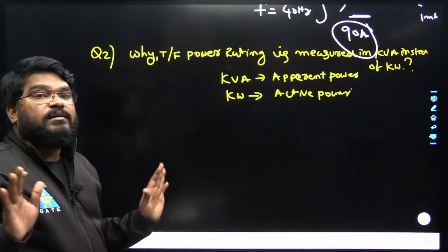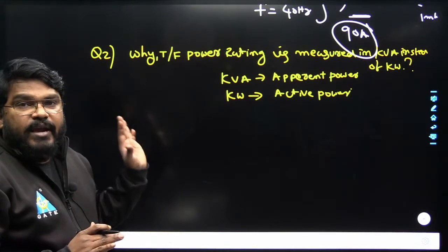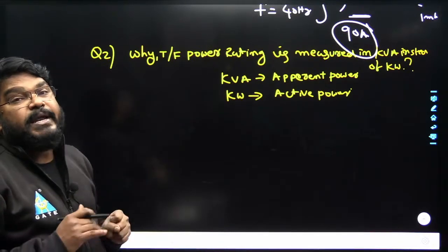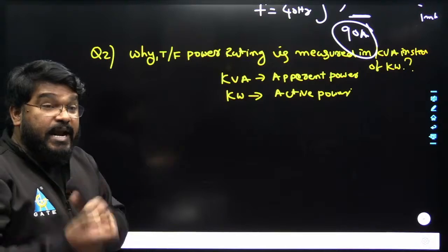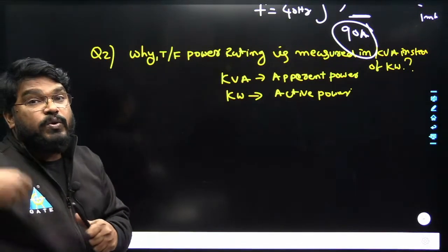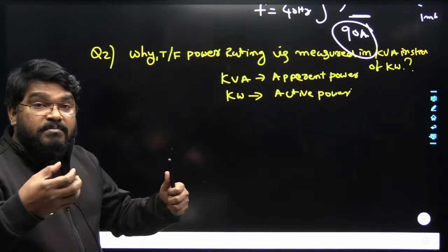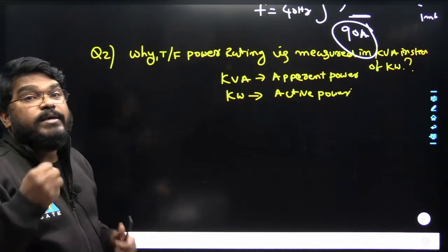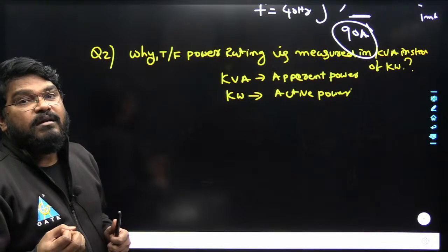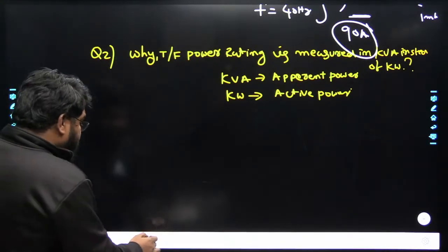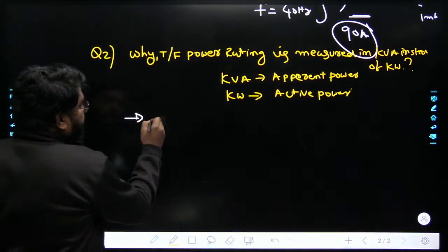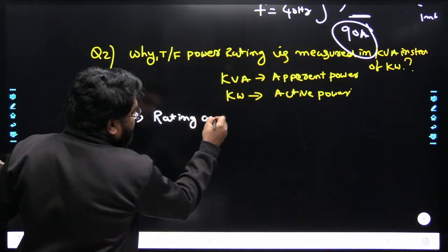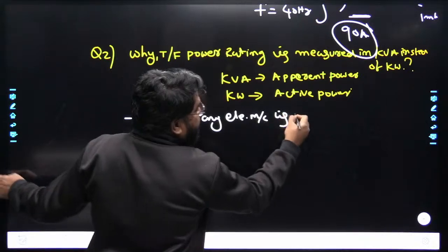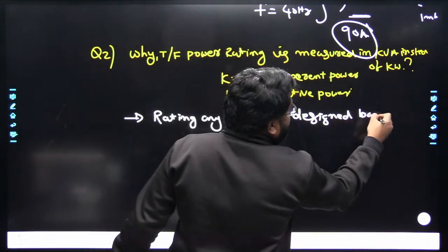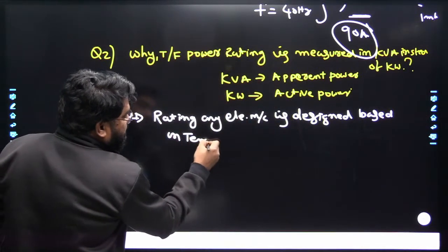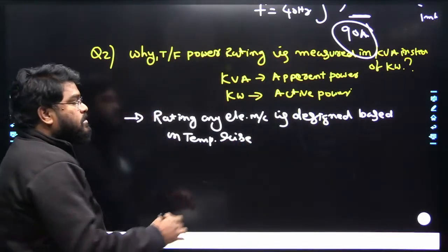The rating of any electrical machine, not only the transformer, is designed based on temperature rise - that is, how much temperature rise occurs. During operation of the transformer, the temperature rise that occurs is known as the temperature rise, and technically we can call this the losses of the transformer. So the rating of any electrical machine is designed based on temperature rise, and temperature rise means the losses.